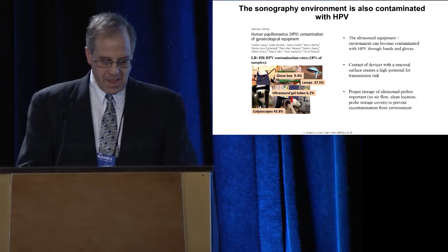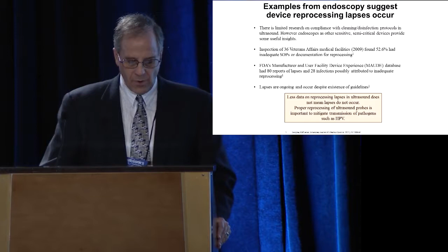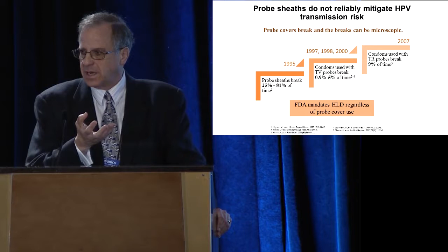So there are many examples from endoscopy suggesting that device reprocessing lapses occur. We heard a little bit about that, but you can have the best protocols in the world, and if people don't follow them, they're no good. Less data on reprocessing lapses in ultrasound does not mean lapses do not occur, and proper reprocessing of ultrasound probes is important to mitigate transmission of pathogens such as HPV. Now, we heard a little bit about covers on these probes. These probe covers break, they have holes in them. Condoms also have holes, and studies show that even though visual observation of the cover shows no breaks or defects in it, there is still contamination of HPV on the probe.